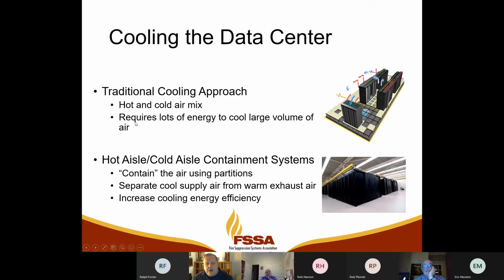So in higher densities, it just altogether requires a lot of energy to cool that large volume of air. And there is a practical limit to where it basically doesn't work. It may cool the bottom three servers, or maybe the bottom third of the servers, well in a rack, but up at the top, those servers up high are going to see some problems. They're not going to be cooled effectively. So that's led us to changes in the data center where we start to have containment systems, where we use additional material to contain the air and start to separate the hot from the cold to increase the cooling efficiency.